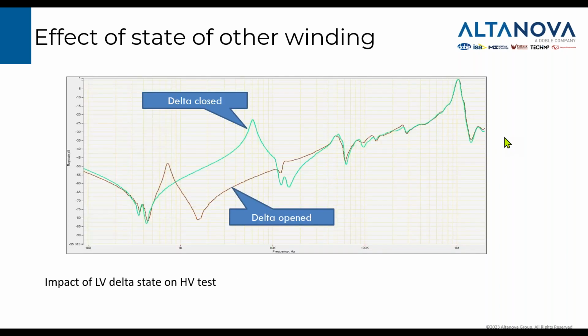Here another situation of effect of another winding. This was generator transformer with LV delta winding brought to the tank in 6 connections. So each coil was brought to tank separately, and the delta was constructed outside the transformer on site. When I tested this transformer, I had that delta completely disconnected, so there was no delta connection, and I just restored the delta by using jumping leads, shorting leads. So here we have two responses, one with delta closed and one with delta opened, as measured on high voltage side, which was not the one which was opened or closed. So again, condition of additional winding plays a role.